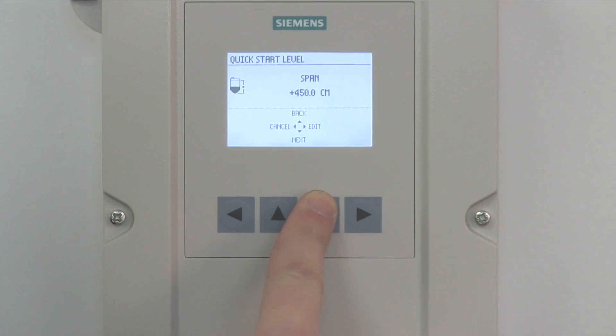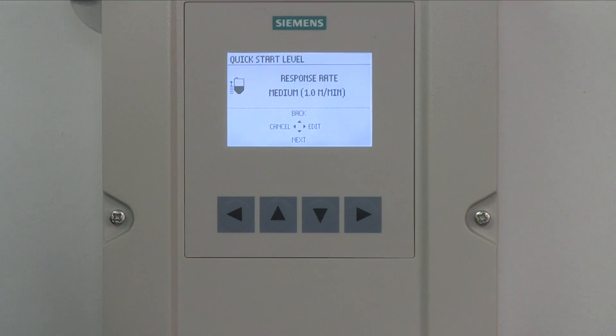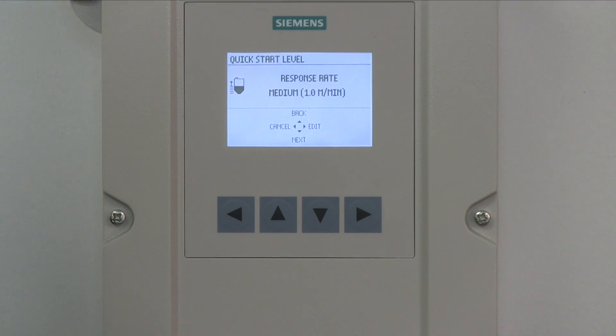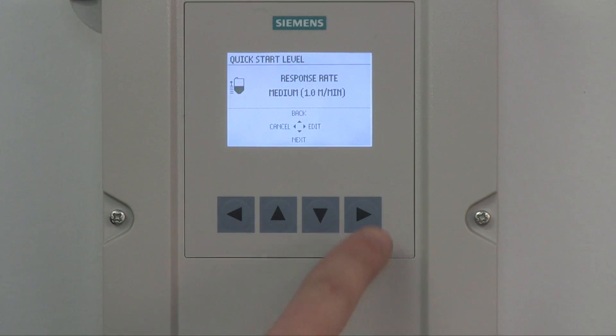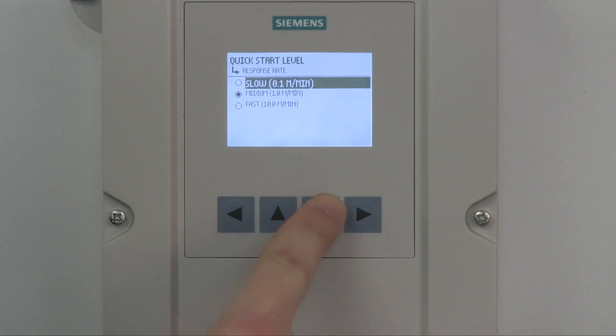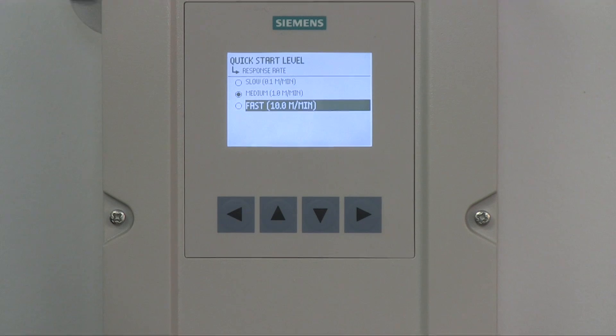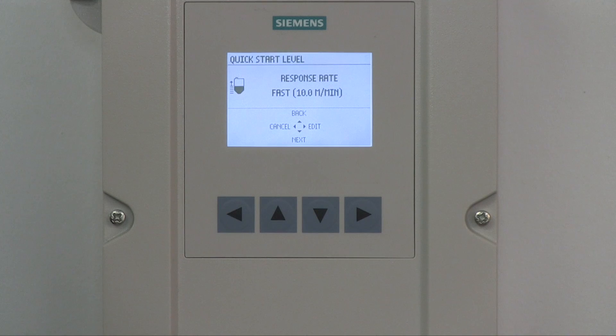Press the down arrow to select Next to proceed to the next wizard step. The next step is to set the reaction speed of the device. The factory response rate default is set to Medium, which is a rate of level change less than 1 meter in 1 minute. Press the right arrow to select Edit to modify this value. There are three options for speed of response: Slow, Medium, and Fast. Your response rate should be set slightly higher than the maximum process response change. Using the up or down arrows, highlight your response rate and press the right arrow to enter your selection. Press the down arrow to select Next to proceed.